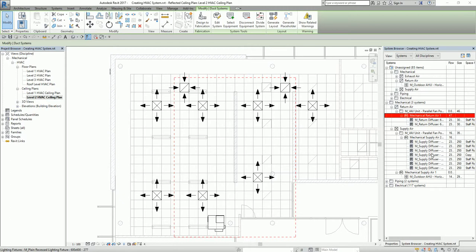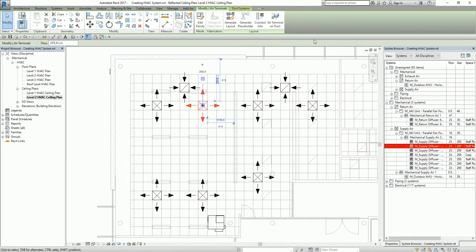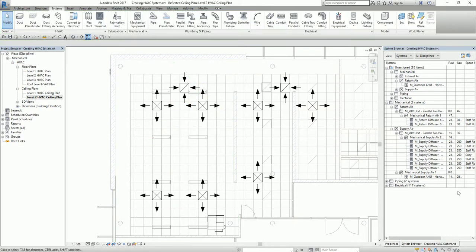That's how you create a system in Revit 2017. Aside from physically connecting ducts to the connectors of your air terminals, you can already create a system by following this procedure. Just remember: insert the component elements first, then select those elements and create the system.